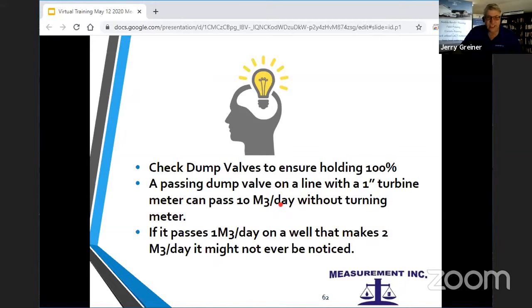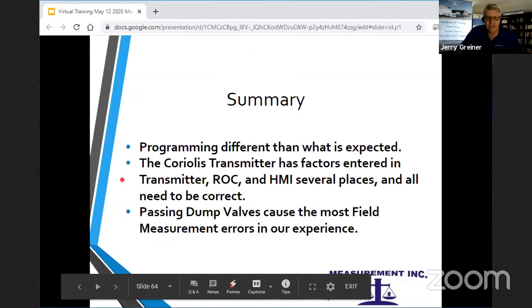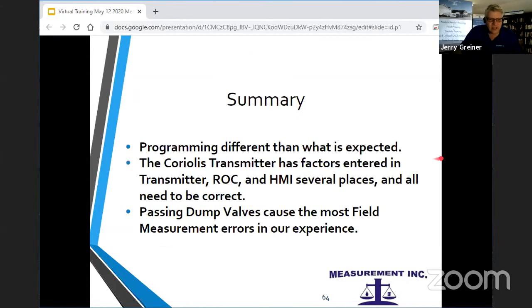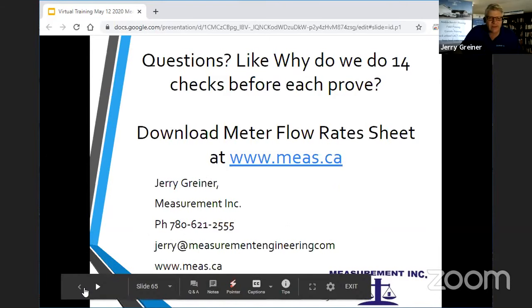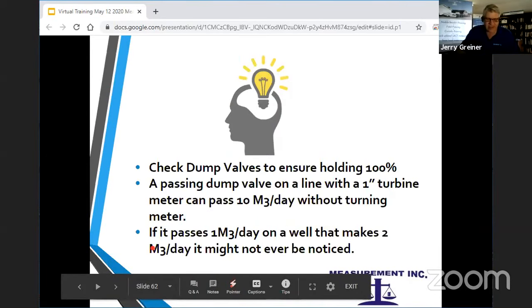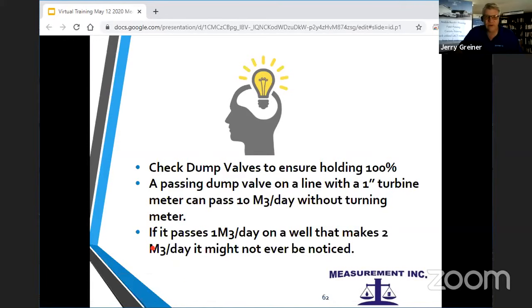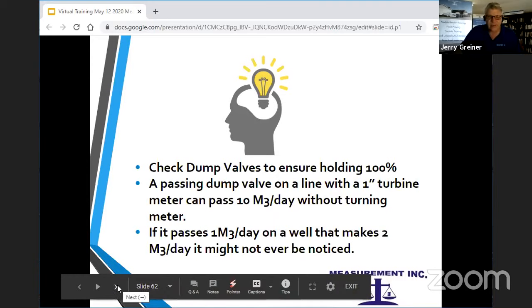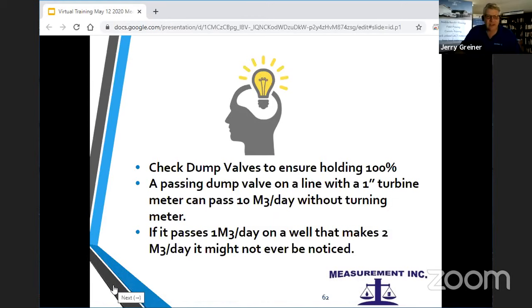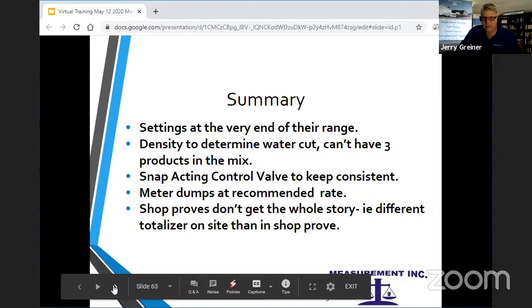It's not that hard to check them. There's different ways. We usually will just put a gauge on the upstream side of the dump valve and close the block valve and see if it holds pressure. If it drops, it's fairly easy to check with a digital gauge, one way or the other, but you want to make sure they hold 100%. And so that's the summary.